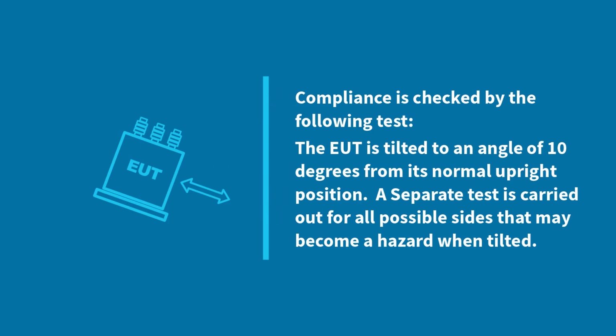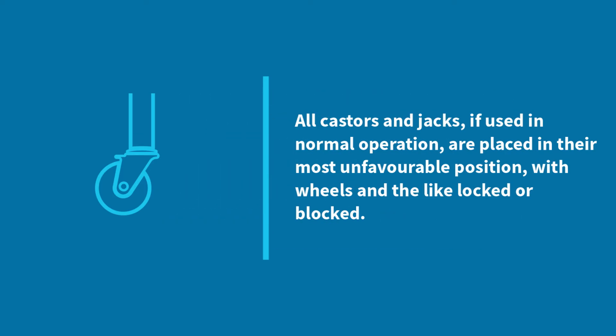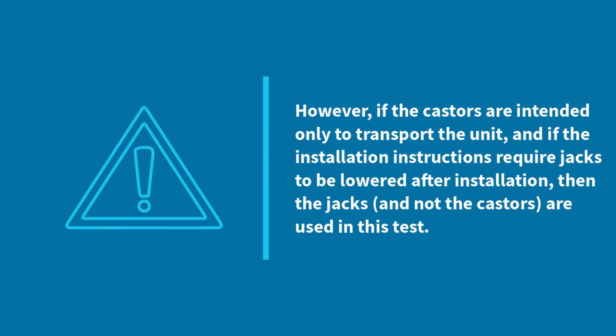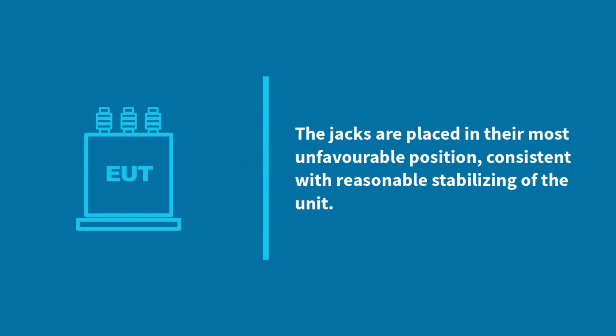Compliance is checked by the following test. The EUT is tilted to an angle of 10 degrees from its normal upright position. A separate test is carried out for all possible sides that may become a hazard when tilted. All casters and jacks, if used in normal operation, are placed in their most unfavorable position, with wheels and the like locked or blocked. However, if the casters are intended only to transport the unit, and if the installation instructions require jacks to be lowered after installation, then the jacks, and not the casters, are used in this test. The jacks are placed in their most unfavorable position consistent with the reasonable stabilizing of the unit.